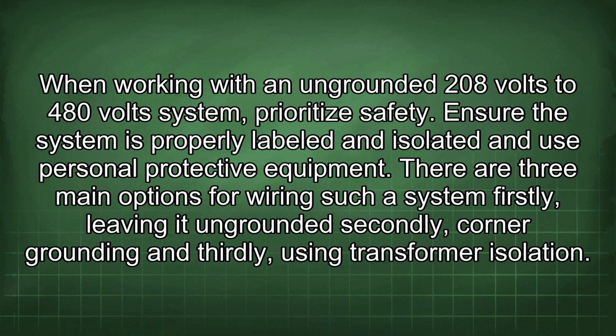When working with an ungrounded 208 volts to 480 volt system, prioritize safety. Ensure the system is properly labeled and isolated and use personal protective equipment. There are three main options for wiring such a system. Firstly, leaving it ungrounded. Secondly, corner grounding. And thirdly, using transformer isolation.